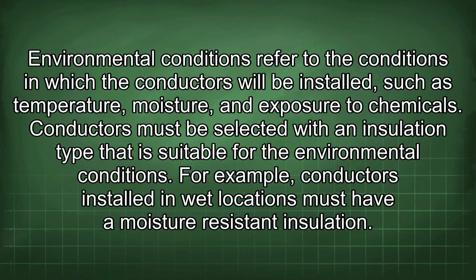Environmental conditions refer to the conditions in which the conductors will be installed, such as temperature, moisture, and exposure to chemicals. Conductors must be selected with an insulation type that is suitable for the environmental conditions. For example, conductors installed in wet locations must have a moisture-resistant insulation.